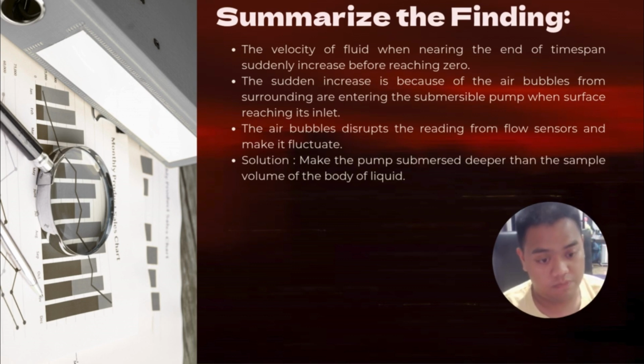This is because when the pump supplies the water to the flow meter, the water inside the vessel will be decreasing and nearing the inlet of the pump. When the surface is suddenly near, the bubble from the surrounding enters the pump. This will create a disruption in the supply tube, causing the sensor to be disrupted and make the reading fluctuate. Our solution here is to make the pump submerged deeper than the sample volume of the body of the liquid.